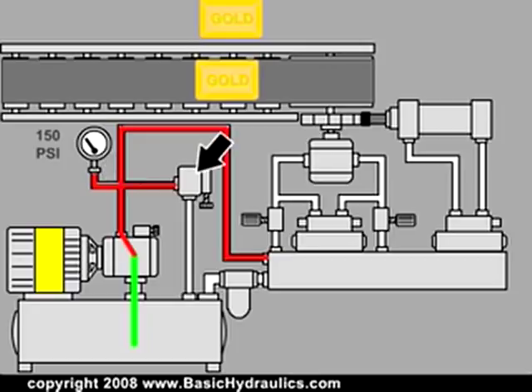The relief valve is a safety device. If the system pressure gets too high, instead of having a line break or a fitting split, hydraulic fluid spills over the relief valve and back to the tank.